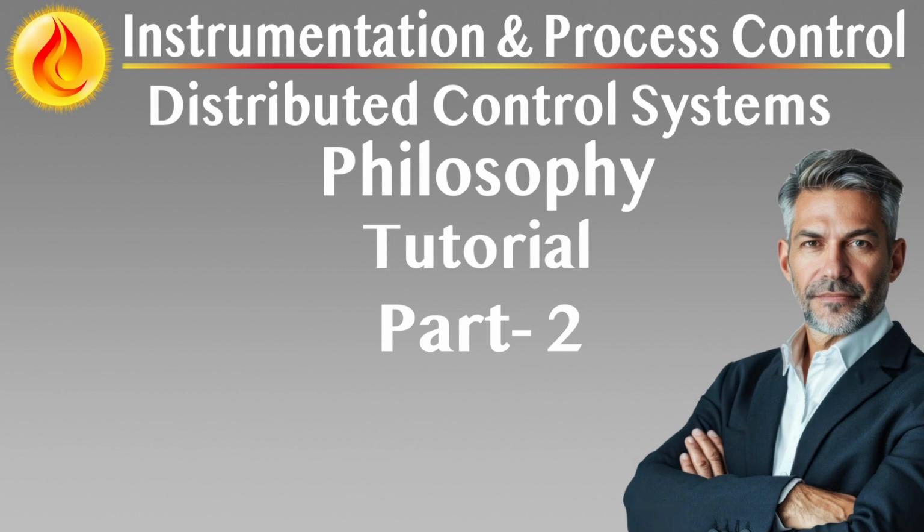Compliance and cybersecurity. Standards-based safety management. The ESD system is designed in compliance with IEC 61511 lifecycle processes, including hazard and risk analysis (HRA), safety requirement specifications (SRS), safety instrumented function allocation, and safety integrity verification. Integrated cybersecurity measures. All networked components follow ISA/IEC 62443 zones and conduit segmentation, intrusion detection, and anomaly logging. No ESD action can be initiated or disabled over unsecured or unvalidated paths.